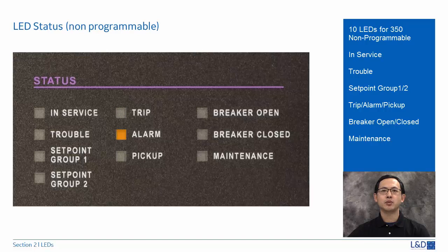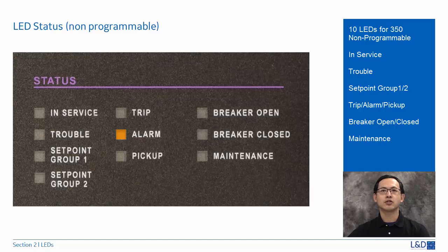Alarm LED will flash in orange color upon detecting an alarm condition with element function selected as alarm. The LED will automatically turn off if the alarm condition clears. The LED will remain steady on if the function of the operated element is selected as latched alarm.